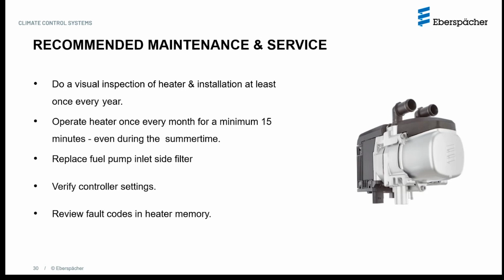This is recommended. Now again, you may decide and say, all right, this is not required by us because we have not run into issues where the filter has been choked and caused the heater to fail constantly. So we have never run into that problem. And you might say, okay, we will do it only when it fails, and we leave it up to the customer.